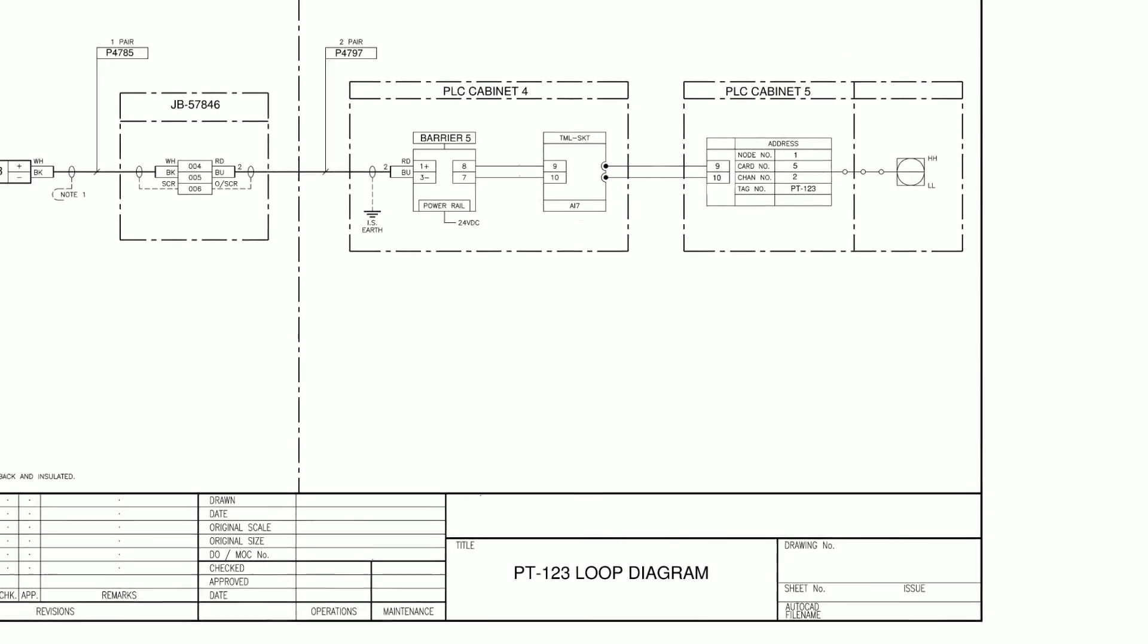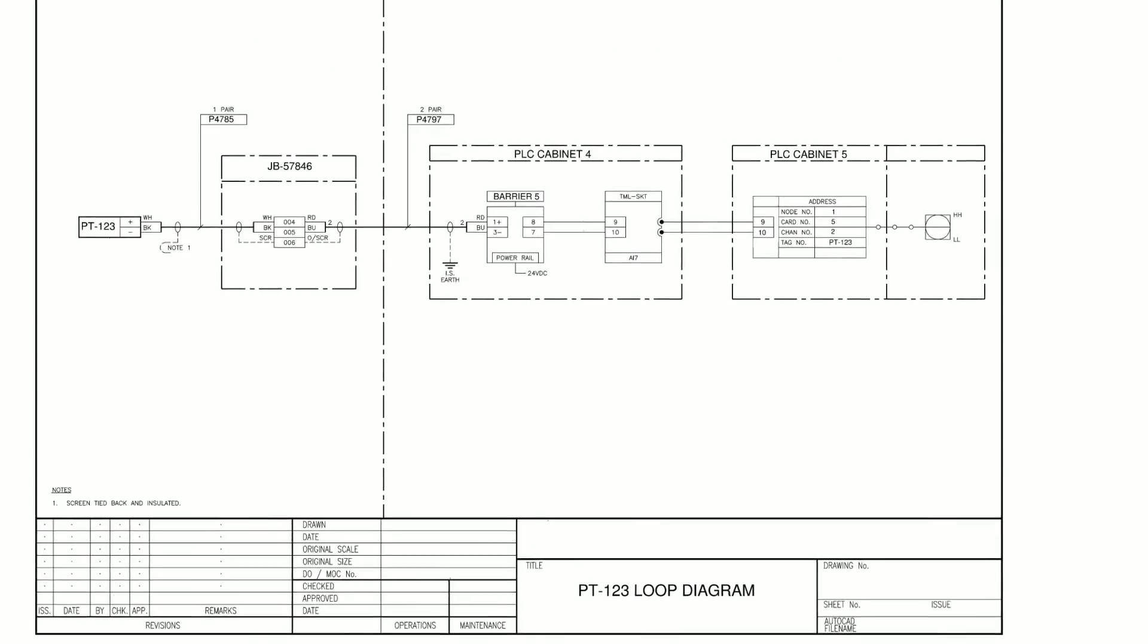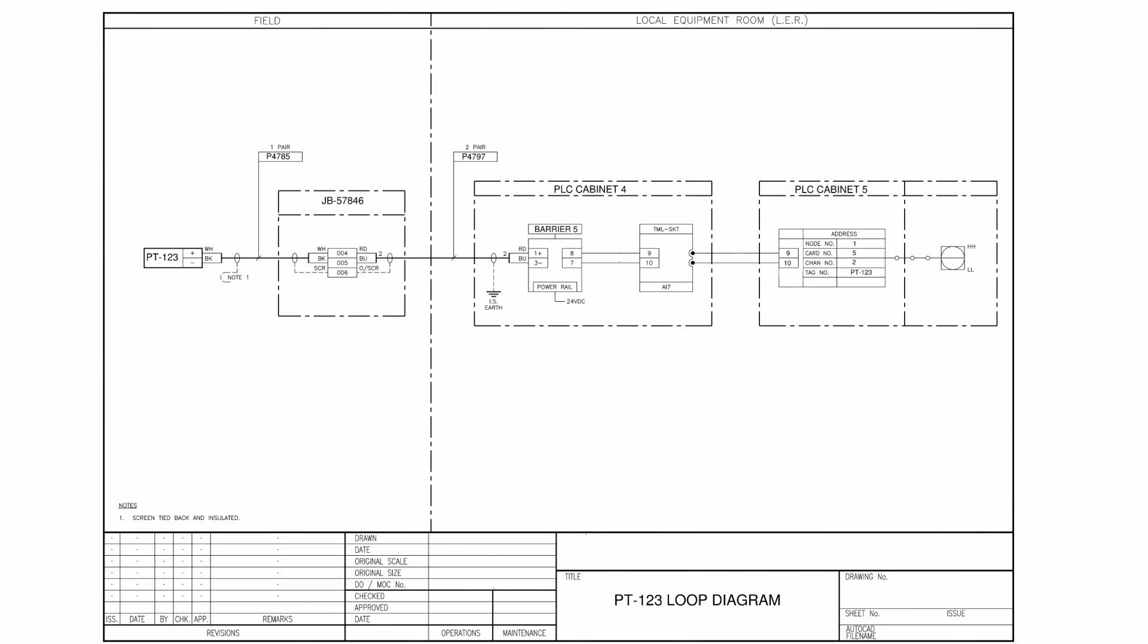You often see drawings have a revision or issue number. Drawings that have been previously printed may not be the latest revision if you find them in the bottom of an electrical panel for example. If you have a drawing and are in any doubt of its validity speak to your supervisor or check yourself on the drawing document management system if you have access to compare the version that you have with the version that's on the system to ensure you have the latest up-to-date information.